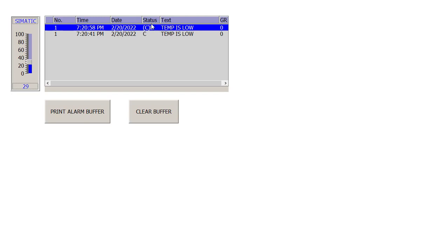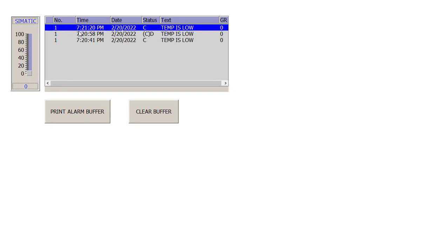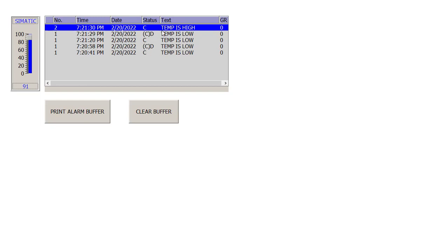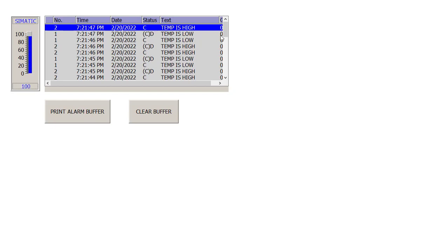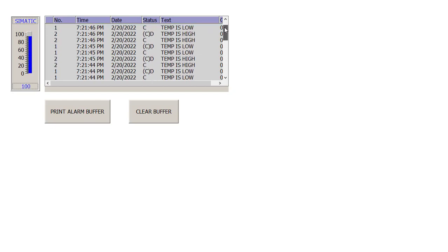When I move the value above 20, the alarm is deactivated — shown with a 'D' for deactivated. The buffer shows timestamps: when the alarm was active and when it was deactivated. Dropping the temperature again re-triggers the alarm. Moving above 80 triggers the temperature high alarm, and dropping below 80 deactivates it. All these activate and deactivate events are logged in the buffer.